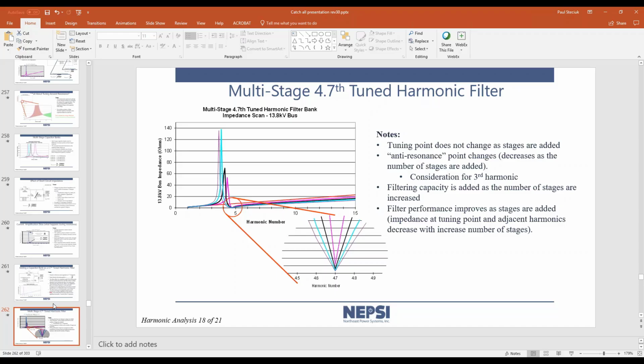And the reason you're doing that is that if you look at all these curves, and these represent the curves of a 1, 2, 3, and 4 stage harmonic filter system, you can see that the tuning point is defined. That does never change. The tuning point will not change. That's a defined point in an impedance curve. And by setting that point there, you have ensured that there is no resonance at the 5th harmonic. You have precluded resonance at the 5th by tuning a filter to the 5th harmonic.